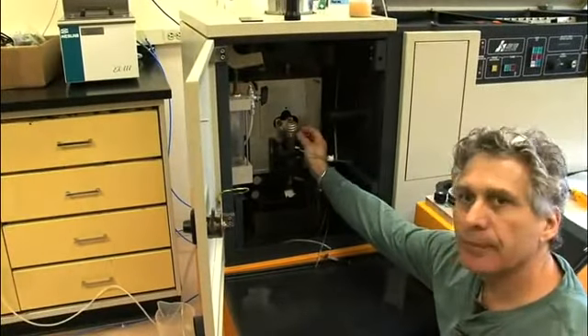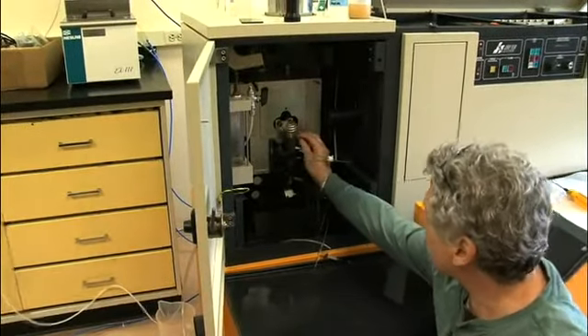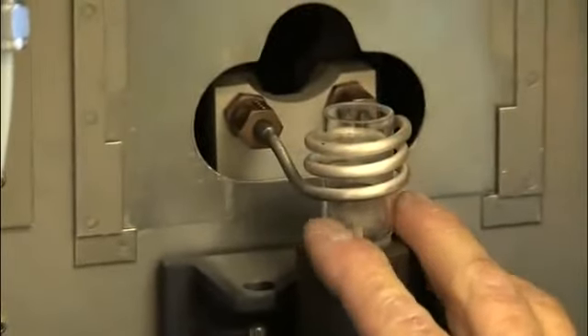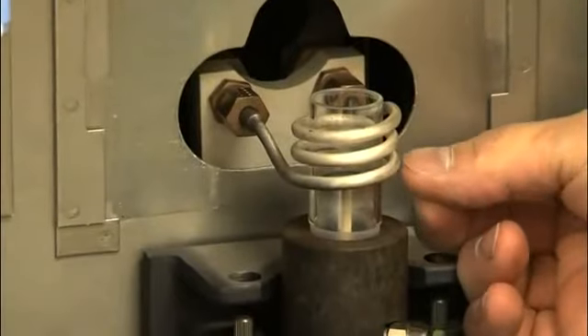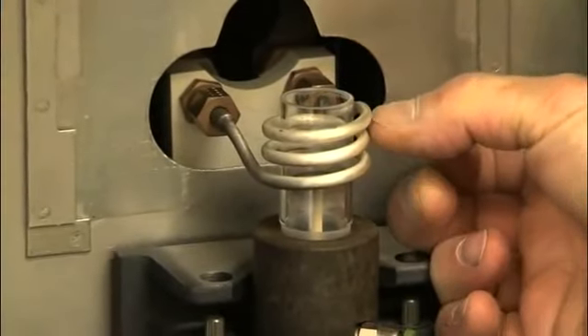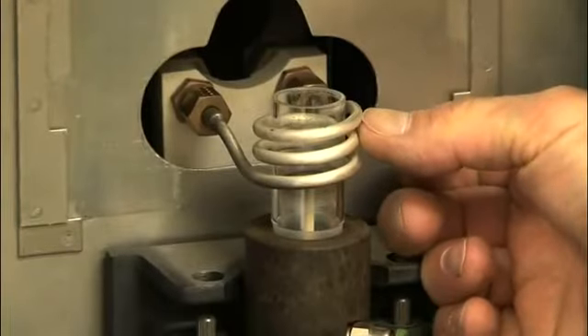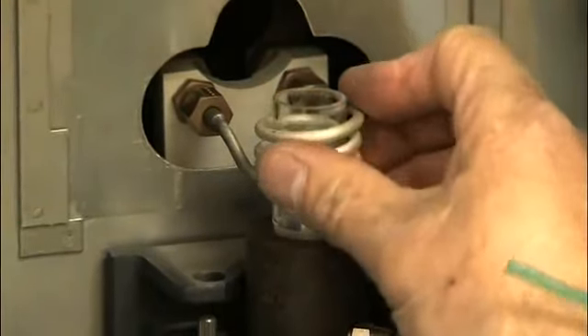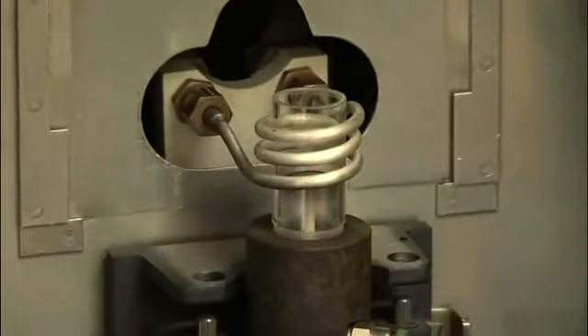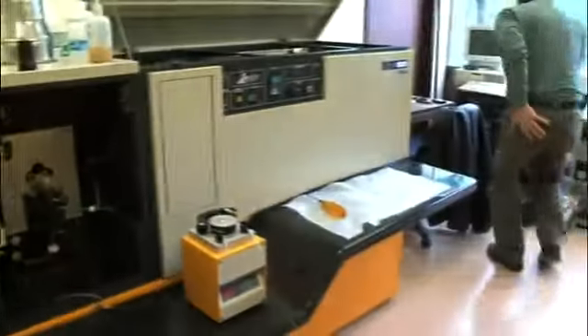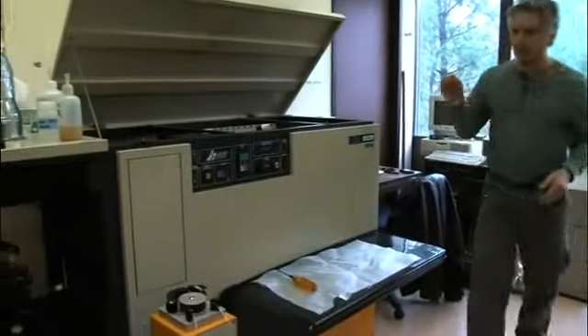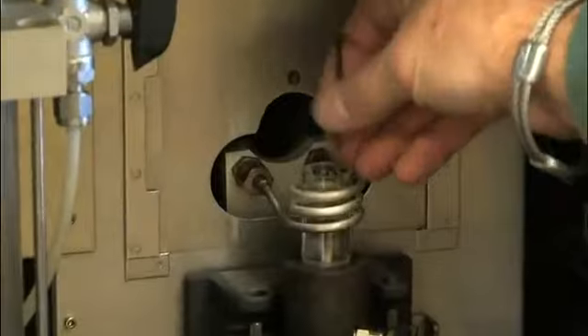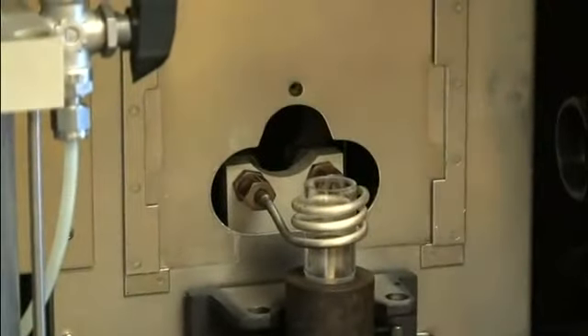Torch height inside the coil. The inner quartz tube should be like 1 millimeter below the bottom coil. That's how you know your height is right in the coil. Coil spacing should be 15 millimeters from the center of the bottom to the center of the top, plus or minus a half a millimeter, just in case you change the coil. Another thing to check is that none of the quartz tube is touching the coil. So I take a little cable tie, go all the way around, and make sure that it's free. Nothing can touch that.